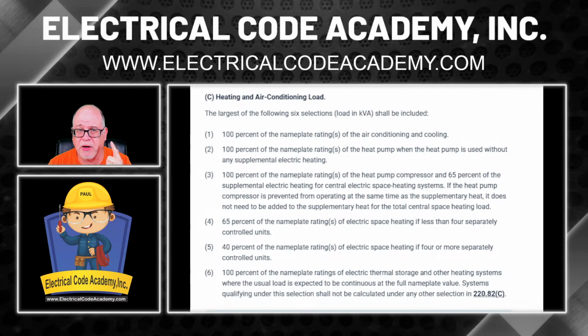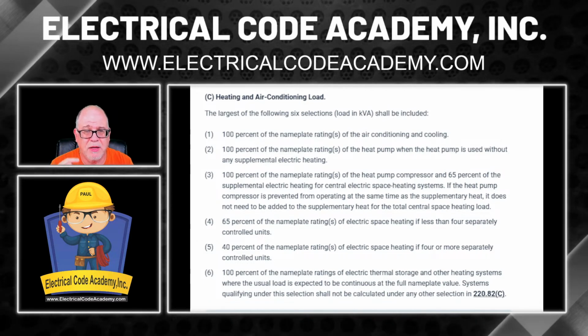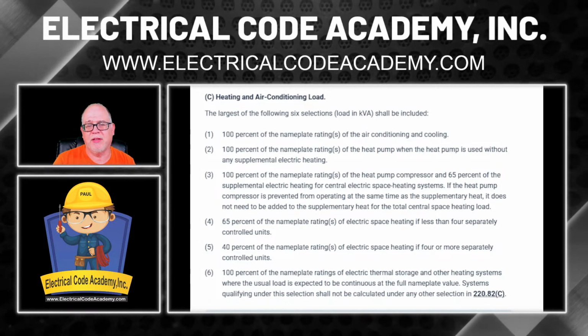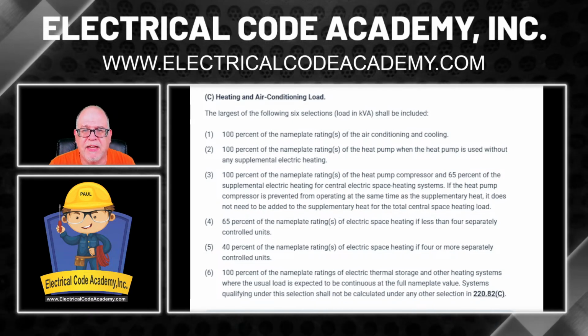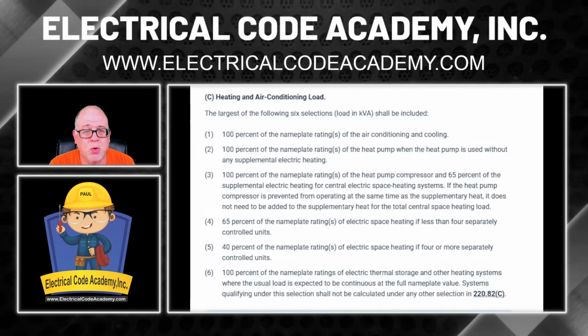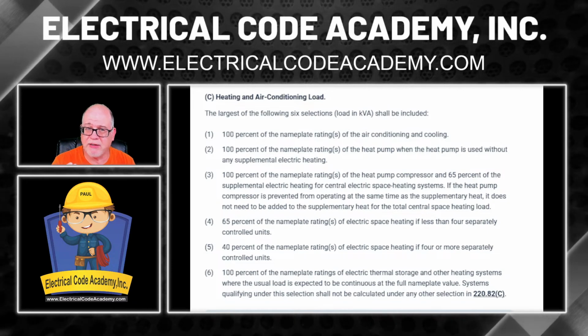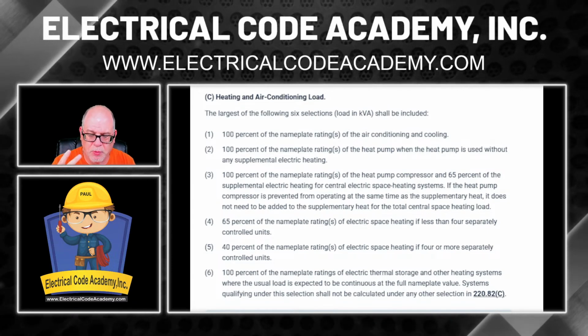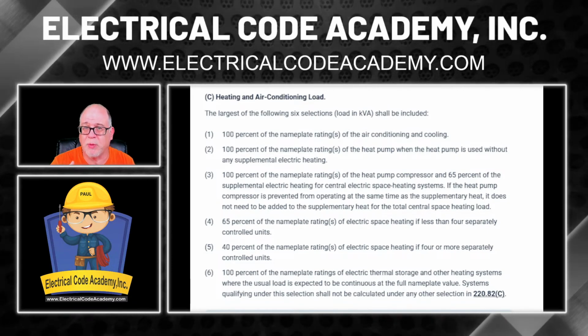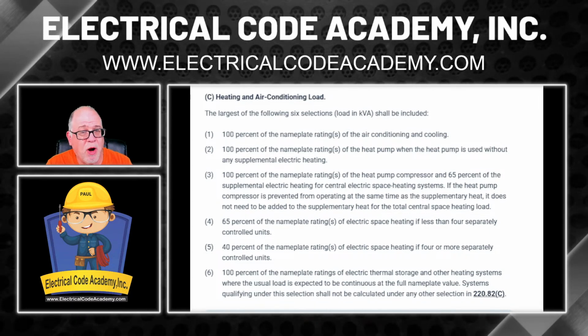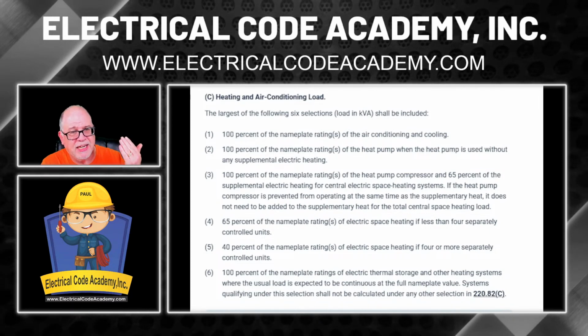Obviously, one is going to deal with air conditioning and the other with the heat. Number 1 on this list says 100% of the nameplate ratings of air conditioning and cooling. We already know what our air conditioning is: we had 2 of them at 10.5 amps and 3 of them at 7.2 amps. And we know our heat: there were 6 of them at 3 kW each.